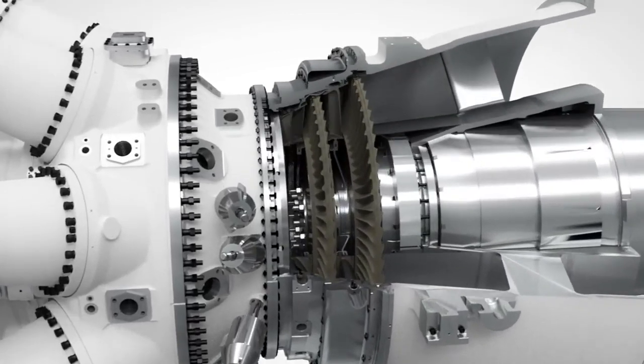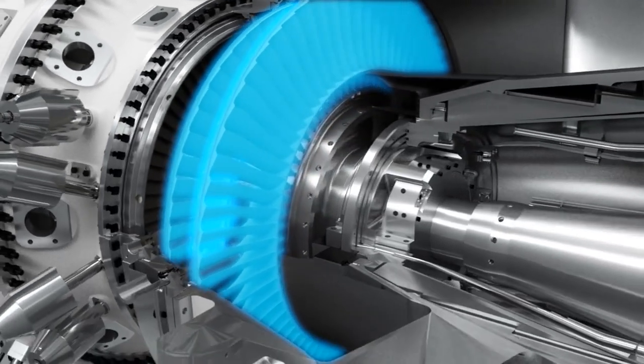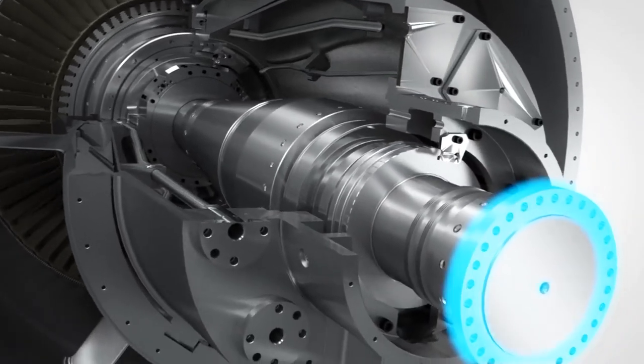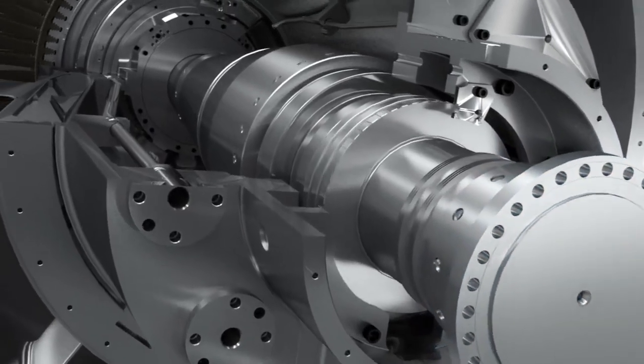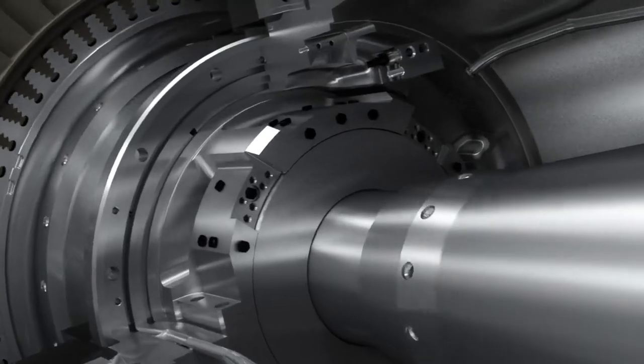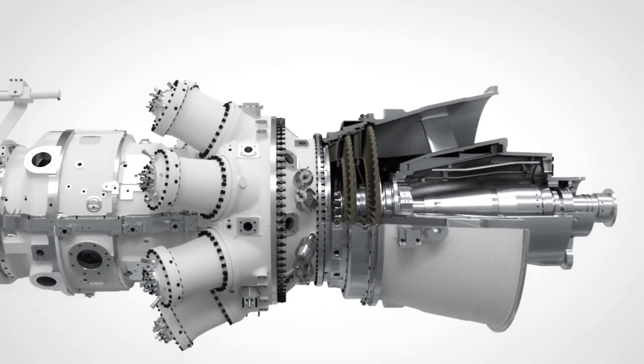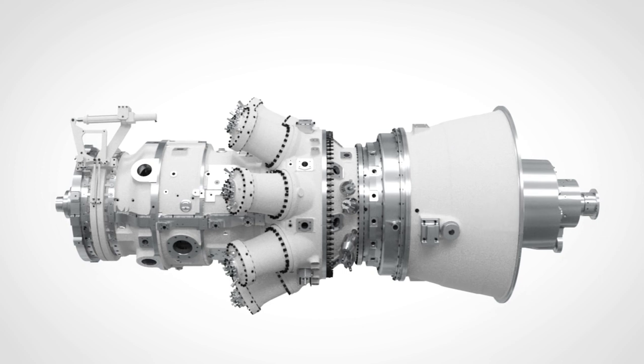The Free Power Turbine is a two-stage high-speed module, nominally running at 6100 RPM. It's equally suitable for mechanical drive application or, with speed reduction gear, power generation. The Free Power Turbine makes the unit an excellent choice where grid requirements call for maintained power output in the event of frequency drops. It can be optimized for all ambient conditions — Arctic, temperate, and tropical climates.